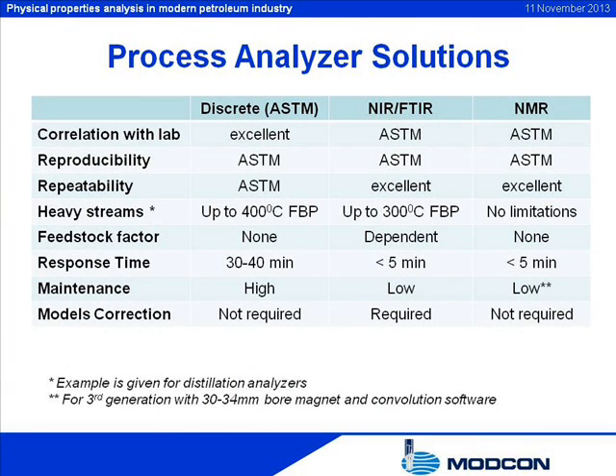ASTM-based discrete analyzers do not depend on crude quality and other factors, resulting in better correlation with the laboratory. However, their response time is longer and maintenance is expensive. For many petroleum applications, using these analyzers is an indisputable requirement, especially when there is a need for online product certification and quality assurance.